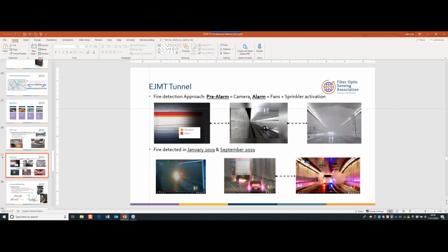Are there any safety concerns when you're using fiber optic systems, perhaps with the laser? Yes, that's a good question. I'll give an example of explosion-proof areas. We tune these systems to have the laser activated in such a way that there will be no problem when, let's say, somebody breaks the cable. There's no problem with the lasers.